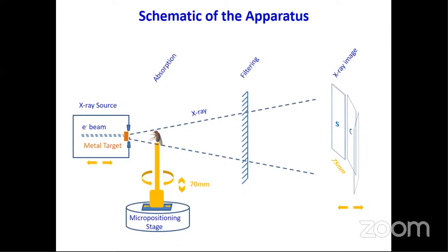As I have mentioned here, the stage can make a vertical travel of about 70 mm, which means we can, in principle, scan a sample which is about 70 mm long. But these fall into certain constraints, which I'll come to in a short while. In addition, the CT scanner gives us an option to pan the camera.